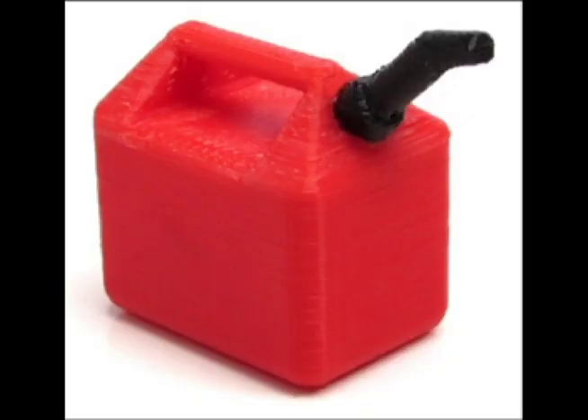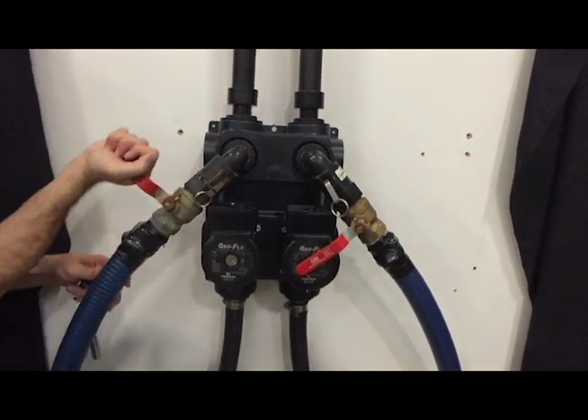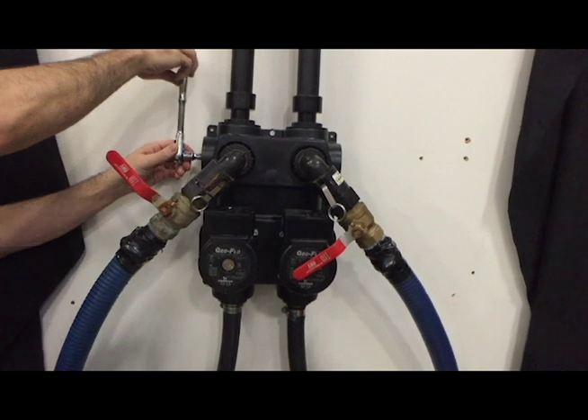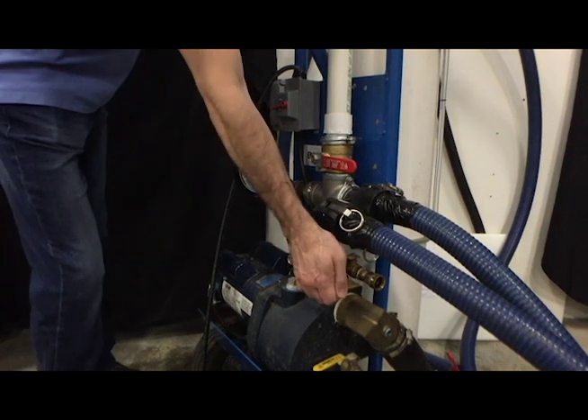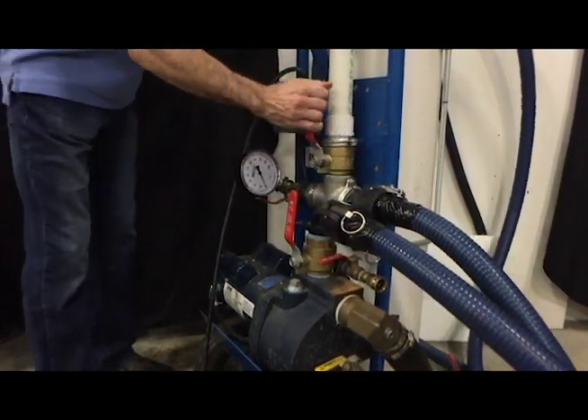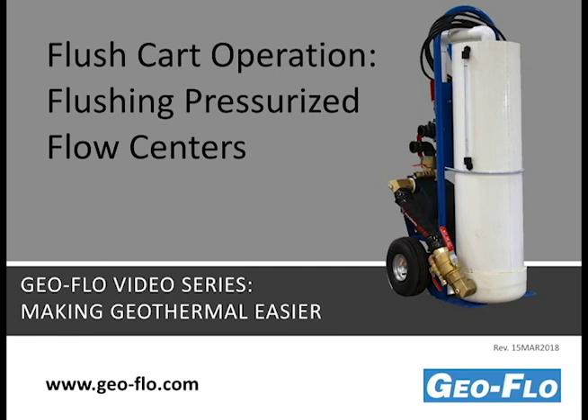If planning to add antifreeze, skip the next few steps and leave the flush cart hoses connected. Otherwise, close the ball valves on the flush cart hoses and rotate the three-way valves so that the flush cart is isolated from the system. The off position will now be facing the flush port. Open the inch-and-a-half supply and return valves to relieve pressure in the hoses. With the ball valves closed on the flush cart hoses, remove the flush cart hoses from the flow center. Thank you for watching the Geo-Flo video series. For more information, check out our website at www.geo-flo.com.